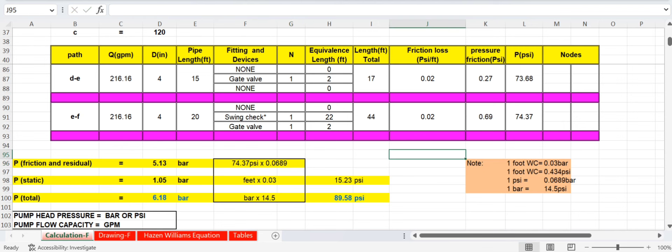The final total friction and residual pressure is 74.37 psi, which converts to approximately 5 bar (multiplied by 0.06895). This represents the combined residual pressure plus total friction losses. The remaining step is to add the static head pressure (Hs) to complete the fire pump head calculation.